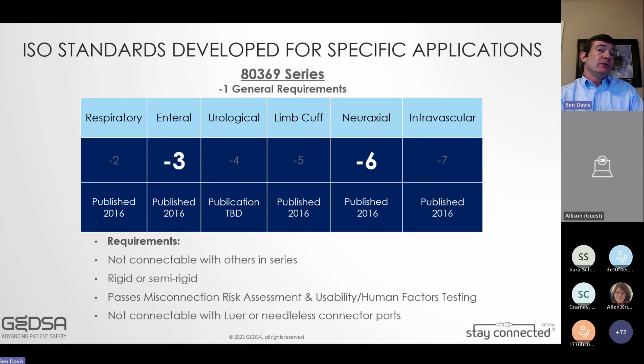A common theme across all of these general requirements is that these are not connectable with other connectors in the series. The connectors must be rigid or semi-rigid. If you think about some of the funnel connectors, like in the enteral space, they're very pliable and soft, and they're able to flex and seal around items that they shouldn't. So every one of these connectors in this series of standards has a hardness requirement where they don't flex like that. They must also all pass misconnection risk assessments and usability and human factors testing, and of course they must not be compatible with Luer or needleless connector ports.